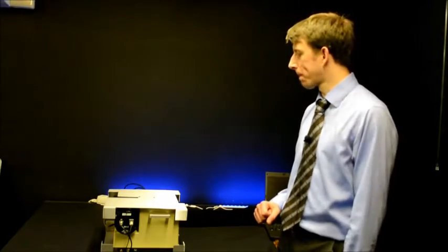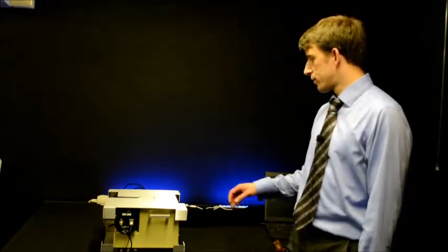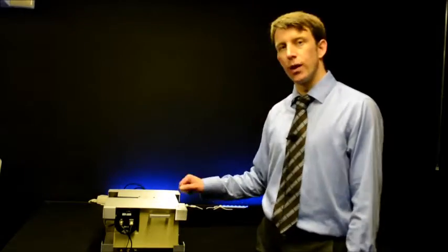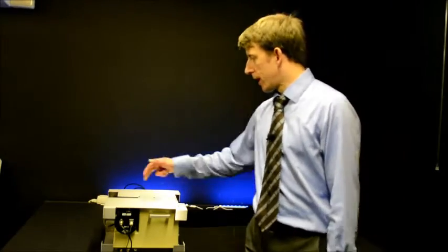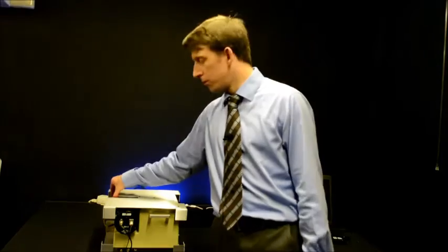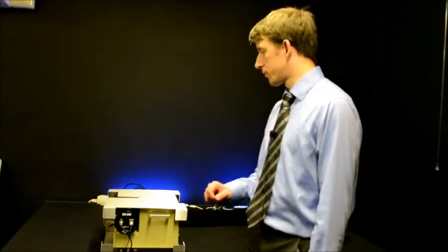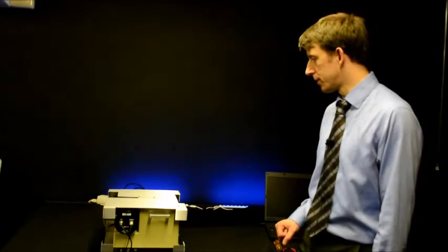The middle slit is not changeable. The system is provided with slits for 1, 2 and 5 nanometer bandwidth, and at the exit of the port for the radiometer mode we have a 1.5 by 5 millimeter rectangle.